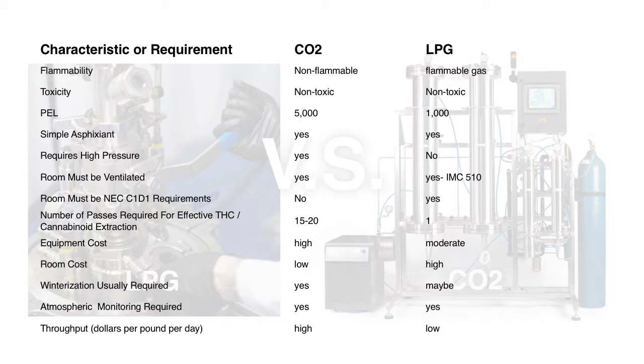Now if we take a look at the electrical requirements for a CO2 room, there are no necessary National Electric Code requirements. You can use standard electrical appliances, whereas in an LPG room, they have to meet the Class 1, Division 1 requirement. Here's one of the major differences. I don't see the number on the LPG side, but it should be one.